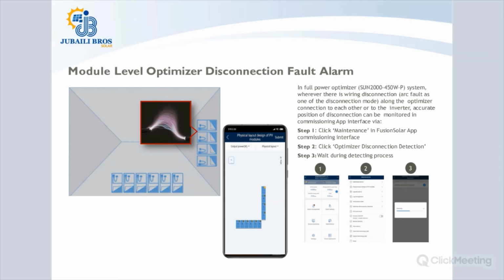And finally, what I have for you is that the PV optimizers from Huawei are not any normal or ordinary optimizers that you can find on the market. They are optimizers that give us module level viewing, allow long strings, and easy and quick optimizer pairing with the inverters. So all these benefits, as we explained right from the first slide, are embedded in this small, robust SUN2000-450W second generation PV optimizer from Huawei.